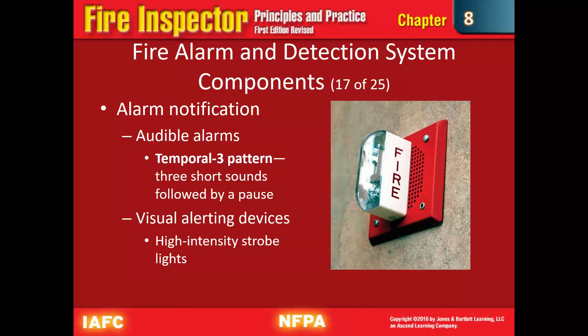Notification devices include audible alarms. The standard alert per NFPA 72 is the Temporal-3 pattern — three short blasts followed by a pause. That is the industry and code standard for alerting devices, so no matter where you hear that sound, you know it's a fire alarm. There's also the visual alerting device — a high-intensity strobe light. Even in midday those are pretty bright and get people's attention, including those who are hard of hearing, letting them know they need to get out.